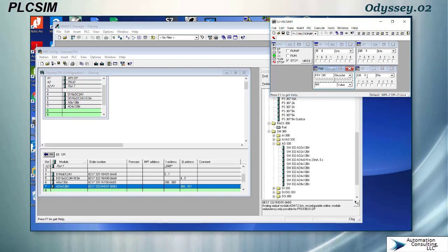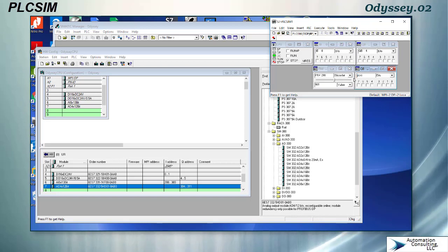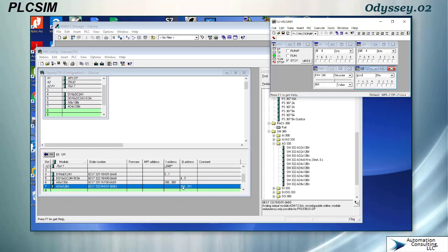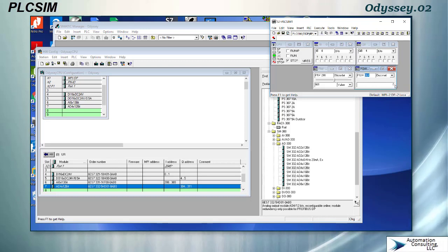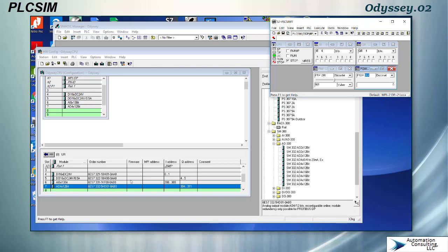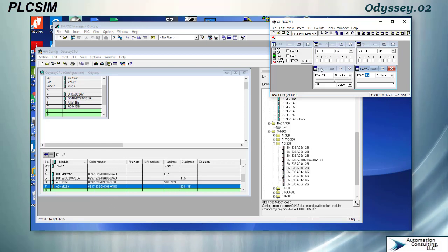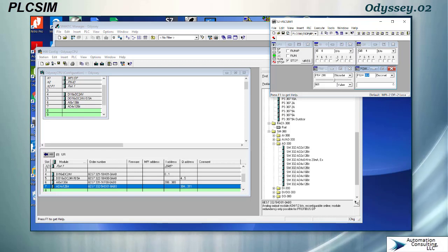On this one it's going to be a PQW for process output word. I look at my address down here and you can see that it starts at 304 so we'll make it PQW 304. The only thing we really care about here is the number that comes out of it. This will simulate something like a voltage output 0 to 10 volts and this will simulate a voltage input 0 to 10 volts. We'll do some scaling with it later. If I want to turn on inputs I just put little checkboxes in there, so it's just like pushing a button on a trainer.